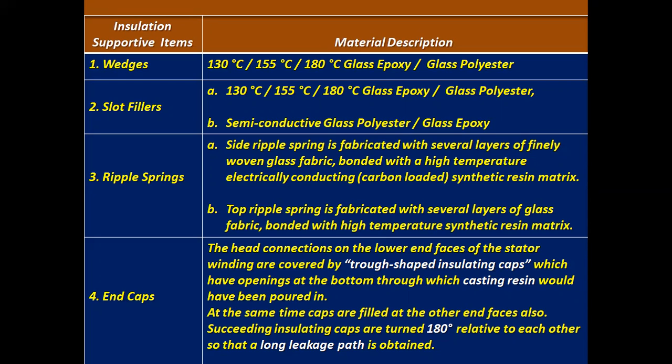A, side ripple spring is fabricated with several layers of finely woven glass fabric bonded with a high temperature electrically conducting carbon loaded synthetic resin matrix. B, top ripple spring is fabricated with several layers of glass fabric bonded with high temperature synthetic resin matrix.